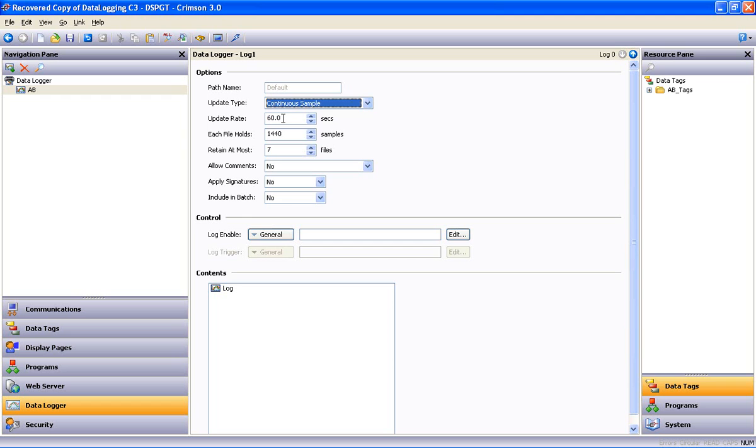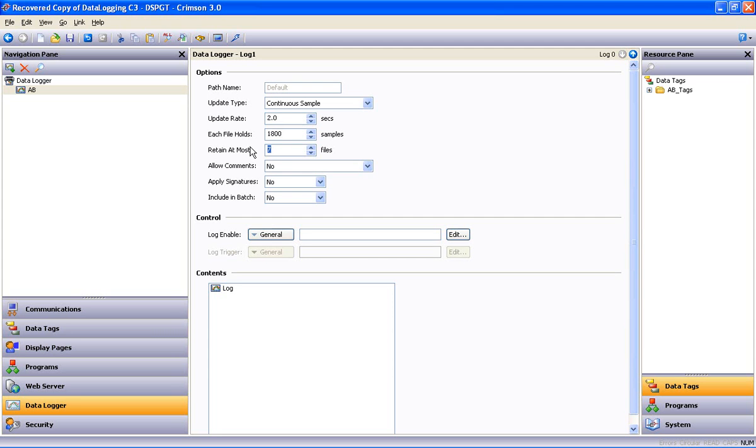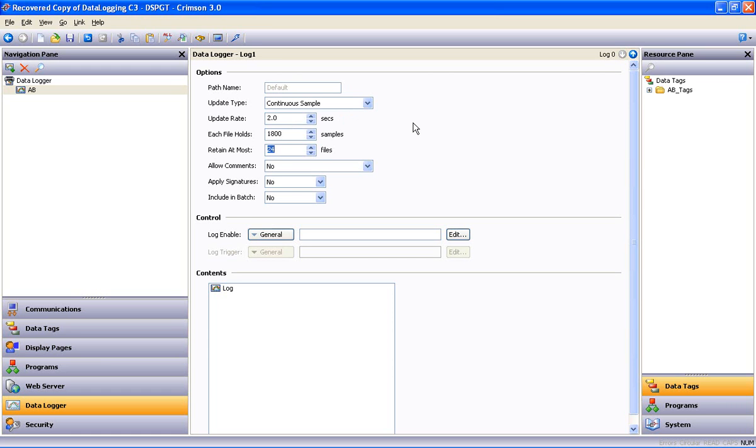The update rate is simply how often you want to record a sample. Let's make that two. How many samples in each file? Make that 1,800. And how many files do we want to create? Make that 24. So, what we just did in this example is set the Data Logger up to log 24 hours of data, with each file representing one hour of samples. Now, since the Data Logger operates on a first-in, first-out basis, when the Data Logger puts the specified number of samples in the last file, it automatically starts overwriting the samples in the first file, so this example always shows the last 24 hours' worth of data.